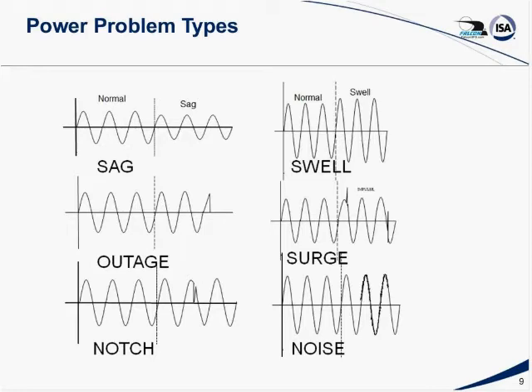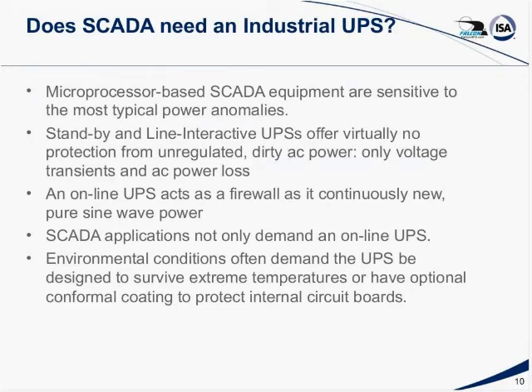Then, Larry, does your SCADA system need an industrial UPS, or does any UPS work? No. SCADA is going to have one designed at least to industrial standards, mainly because, as we'll go through in the operation of UPSs in the next section, with the typical switching, the offline, if you will, UPS, you might as well just buy a surge protector. They offer it, and the interactive, which offers some voltage protection, but they really don't protect you against unregulated or dirty AC power. Only some transients and AC power loss. So as I said, the surge suppressor works as well.